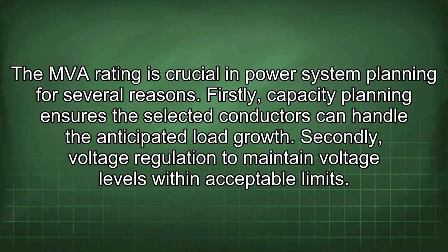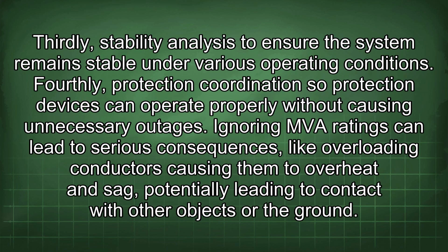The MVA rating is crucial in power system planning for several reasons. Firstly, capacity planning ensures the selected conductors can handle the anticipated load growth. Secondly, voltage regulation to maintain voltage levels within acceptable limits. Thirdly, stability analysis to ensure the system remains stable under various operating conditions. Fourthly, protection coordination so protection devices can operate properly without causing unnecessary outages.